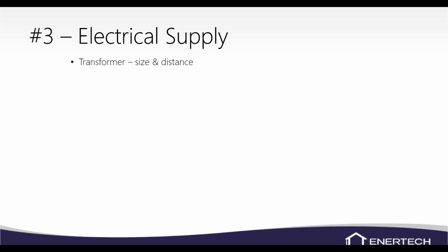Electrical power supply, make sure that they've got a proper transformer, and we're not talking about the transformer in the unit, we're talking about the transformer on the pole. So if they had a gas furnace in their home before and they're installing a geothermal unit, they may need to upgrade their service. So make sure we're always checking that on our electrical power supply.